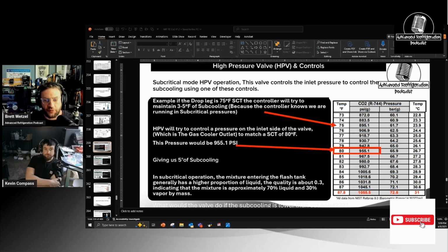So let me talk about this briefly. Basically the HPV has two different modes. We have a subcritical mode, where it's trying to do subcooling. For example, if the outlet of the gas cooler is 75 degrees, it will try to maintain 80 degrees saturated condensing temperature on the CO2 to achieve that 5 degrees of subcooling. That's the first thing it's going to do. Some set points are 3, some set points are 5.